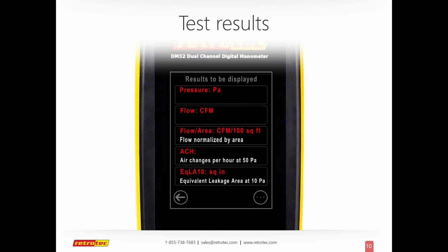So while I'm running my test, I can know right then and there live whether they're passing their air changes per hour or if their CFM per 100 square feet is also passing.